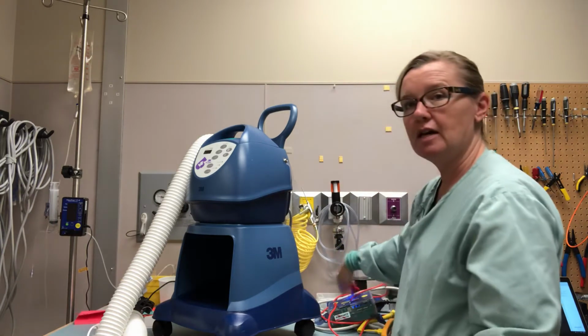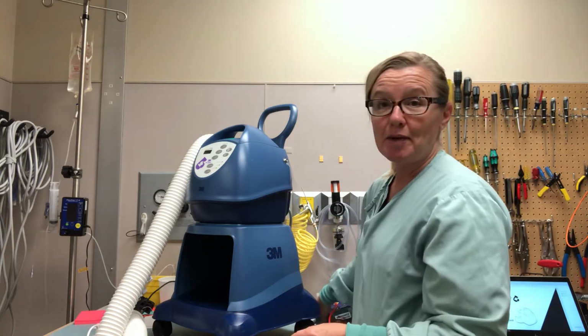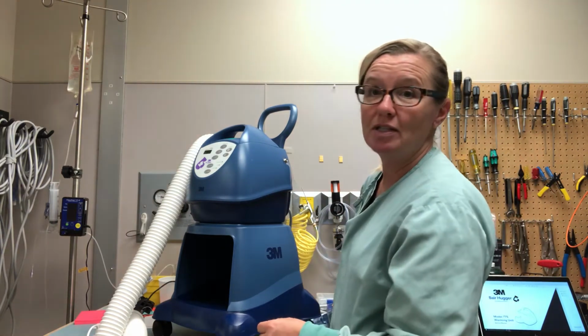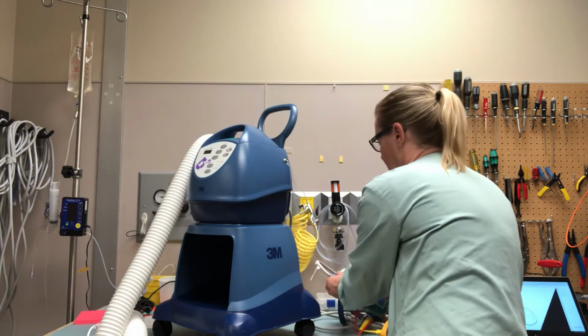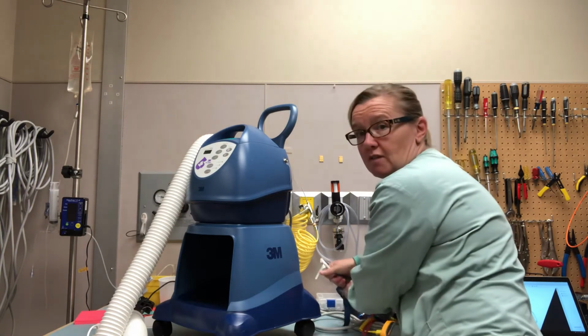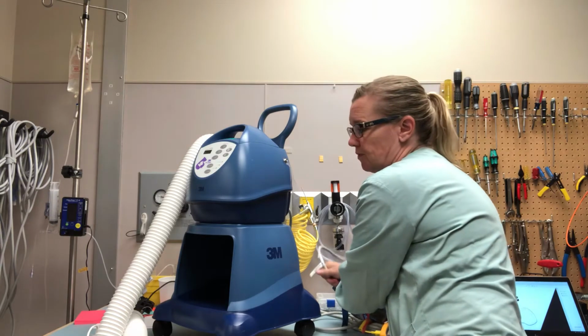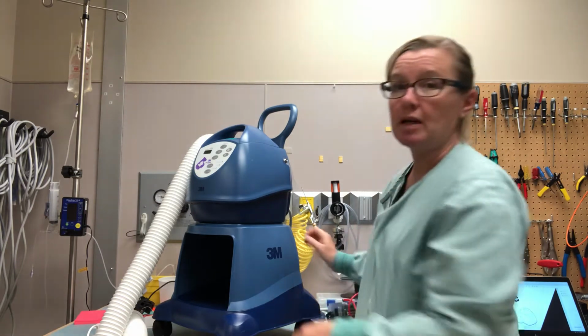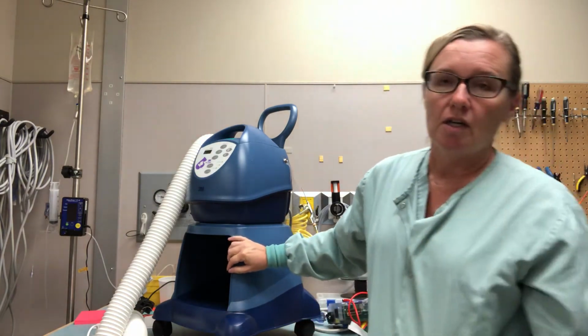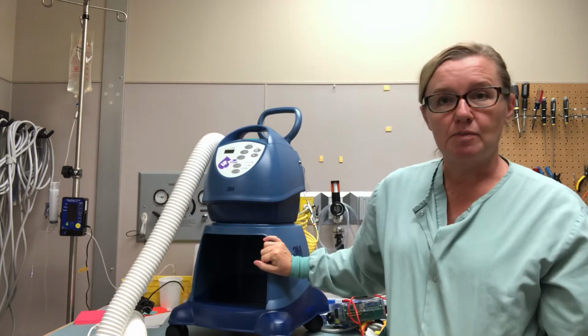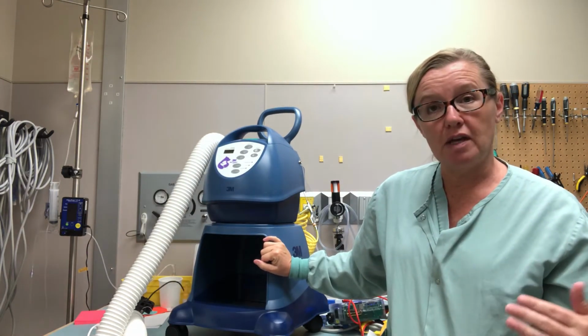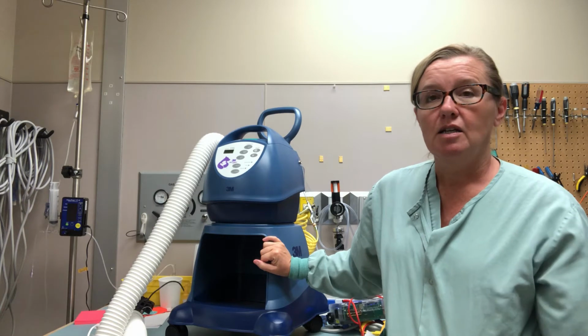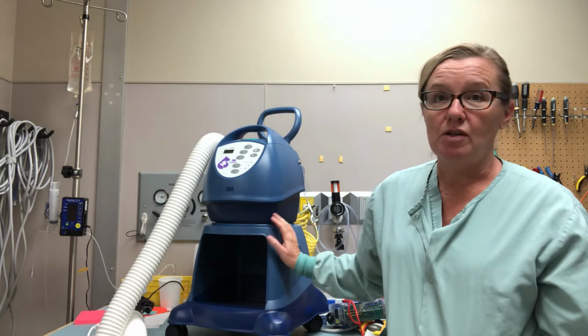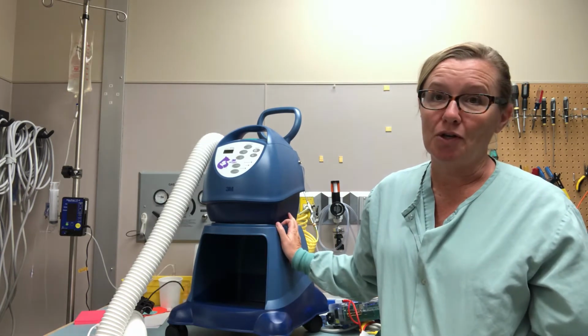I'm going to remove that. I'm going to unplug my Bair Hugger. And next thing I'm going to do is check my filter. According to the manufacturer, the filter is replaced every 12 months or 500 hours. We check ours every 6 months here. The other tests are recommended every 6 months. So while we have the unit in our shop, we're going to check the filter.